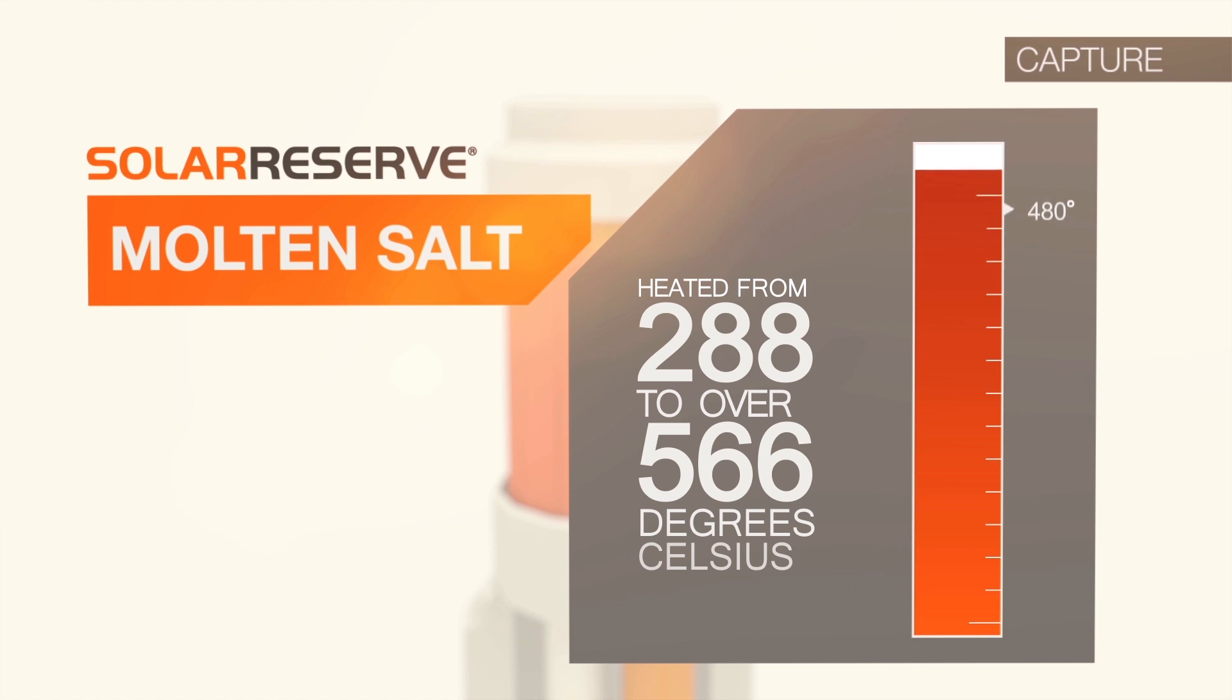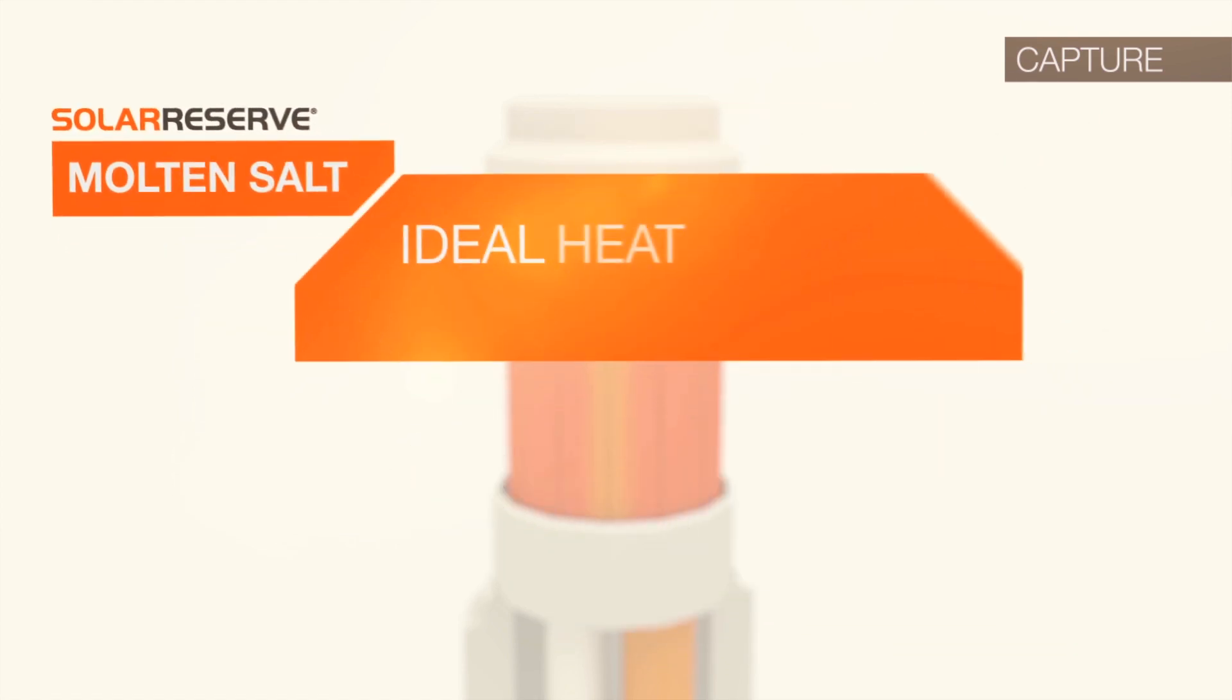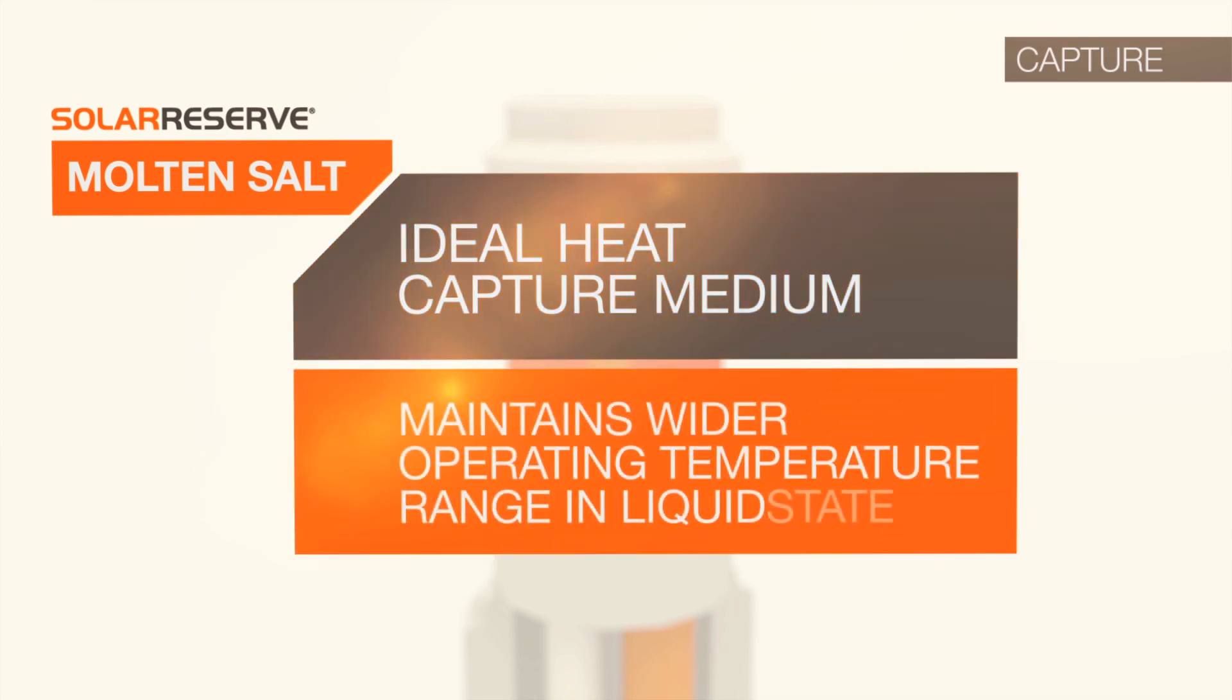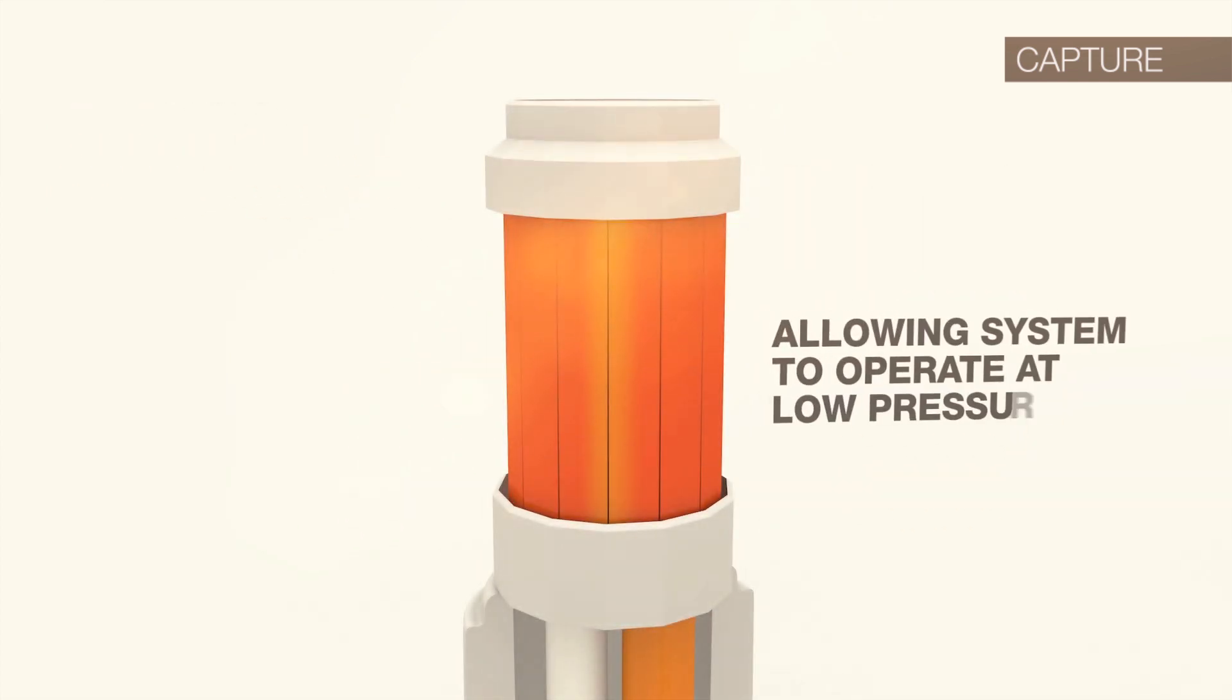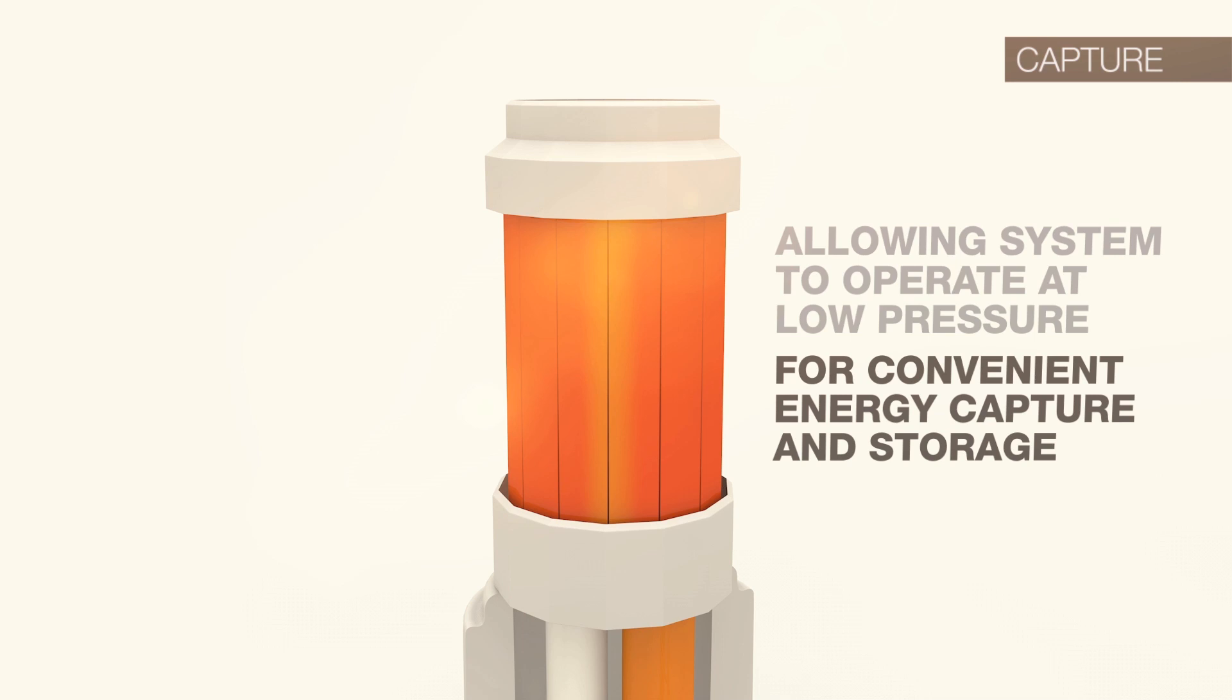In Solar Reserve's technology, the fluid utilized is molten salt, which is heated from 288 to over 566 degrees Celsius. Molten salt is an ideal heat capture medium because it maintains a wider operating temperature range in liquid state, allowing the system to operate at low pressure for superior and safe energy capture and storage.